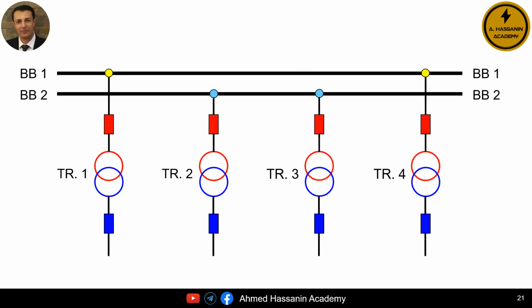Let us assume we have a substation containing, for example, 4 power transformers, and as we can see, transformers number 1 and 4 are connected to bus bar number 1, while transformers number 2 and 3 are connected to bus bar number 2. Let us assume that due to any emergency situation, a short circuit occurred or a fault happened on bus bar number 1, or there was a voltage dip on bus bar number 1 for any reason or due to any transient condition.